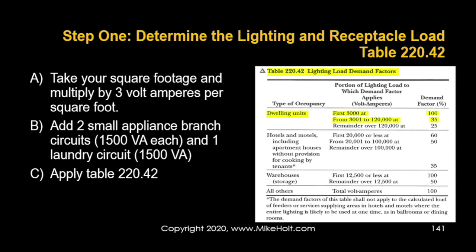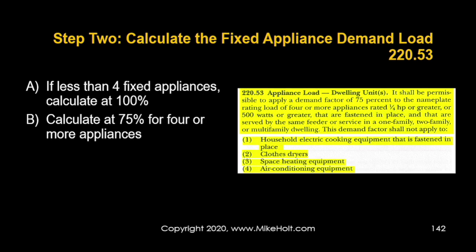Standard method steps: Step 1A — take square footage × 3 volt-amps per square foot. Step 1B — add two small appliance branch circuits at 1,500 VA each and one laundry branch circuit at 1,500 VA. Step 1C — apply Table 220.42 demand factors. Step 2 — calculate fixed appliance demand load: fewer than four appliances at 100%; four or more appliances at 75%, per 220.53.